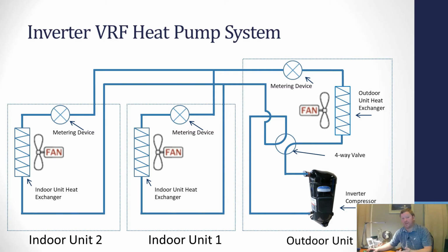Now, when you have an indoor unit, like in the previous example that we'll use indoor unit 1 in the living room that has met its set point, the fan still doesn't shut off. Just like in the mini splits, the fan will ramp down to the low fan speed to try and prevent any unnecessary overshooting. But with VRF systems, you have the ability to turn off the fan. Now when you turn the fan off, it directly affects the amount of heat rejection because there's no fan blowing air across the heat exchanger. So this is huge. I mean, this is the humongous difference between mini splits and VRF systems, because now I'm controlling the demand within 1 degree of the set point instead of 3 or 3.5 or 4 or 7.